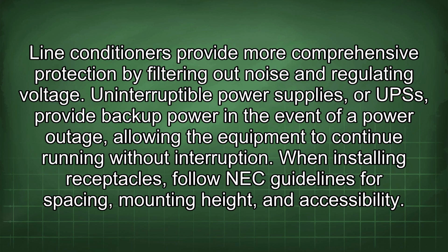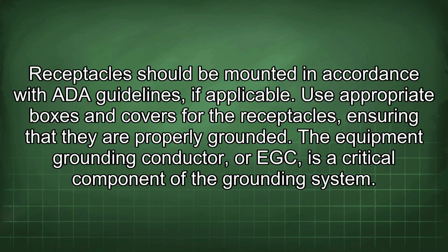When installing receptacles, follow NEC guidelines for spacing, mounting height, and accessibility. Receptacles should be mounted in accordance with ADA guidelines, if applicable. Use appropriate boxes and covers for the receptacles, ensuring that they are properly grounded. The equipment grounding conductor, or EGC, is a critical component of the grounding system.